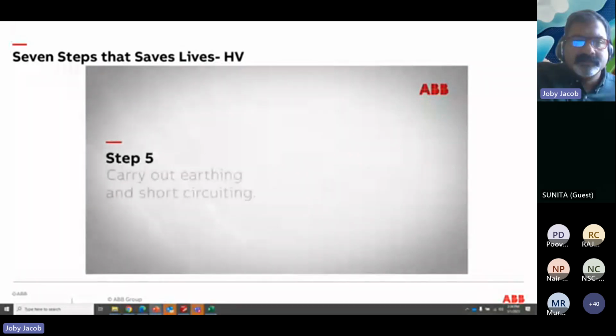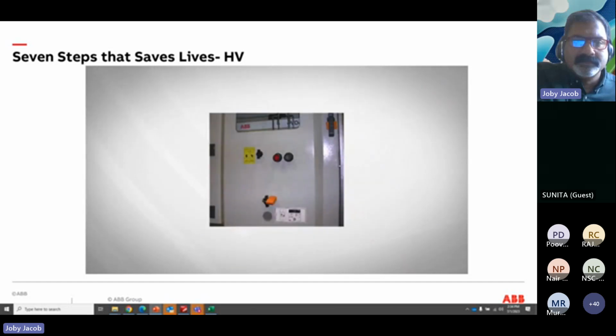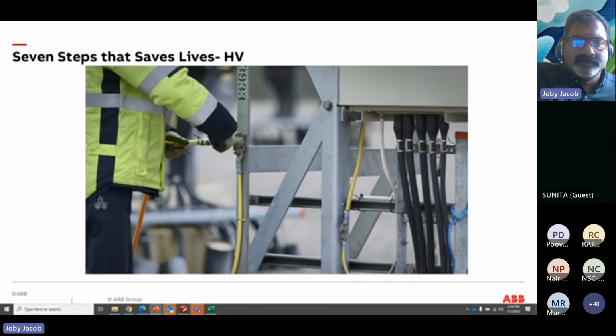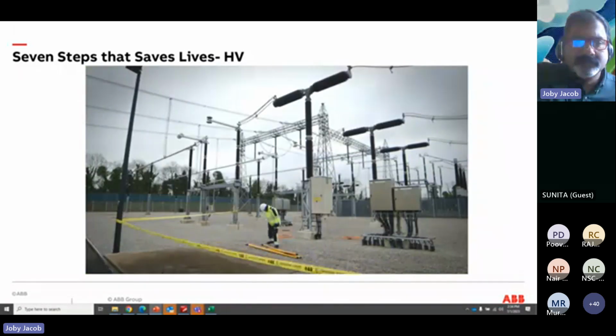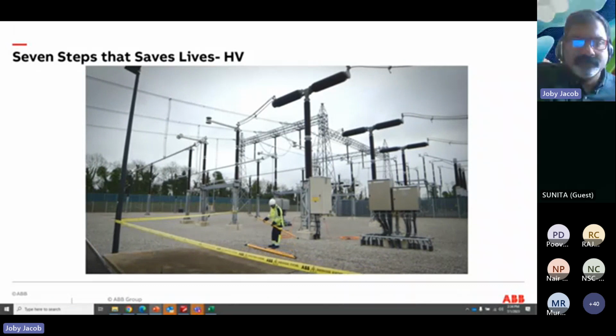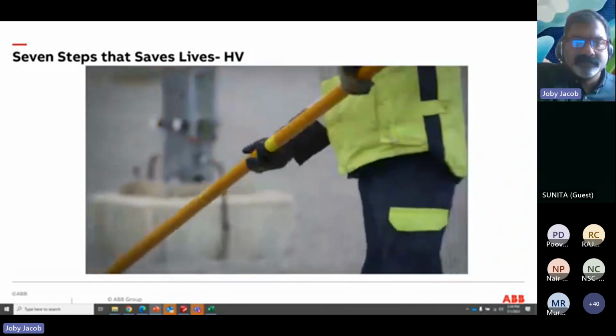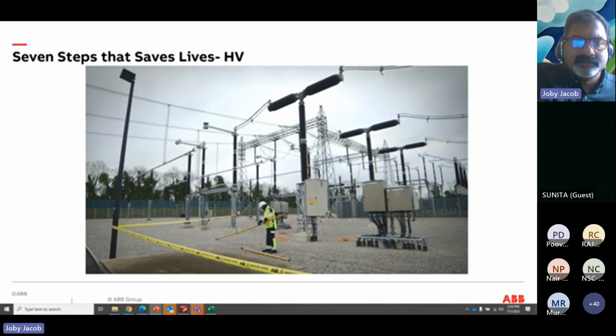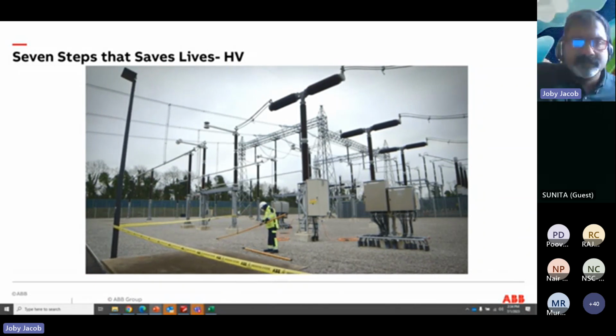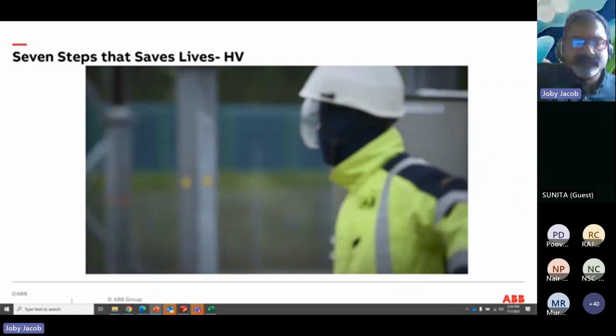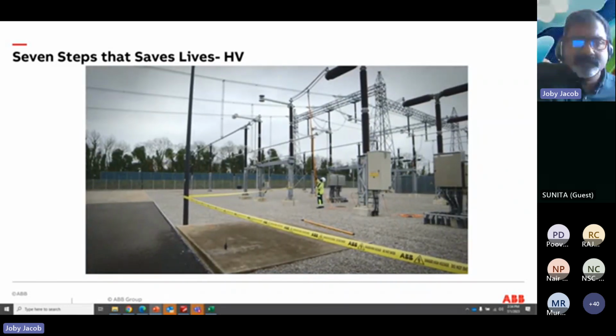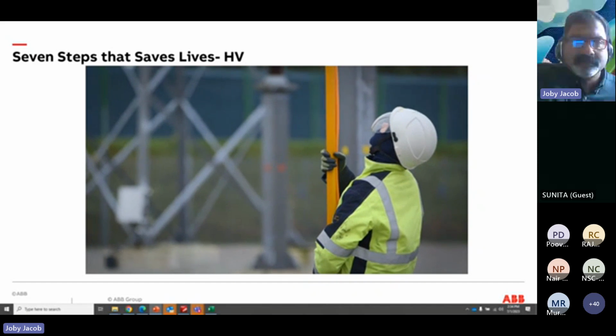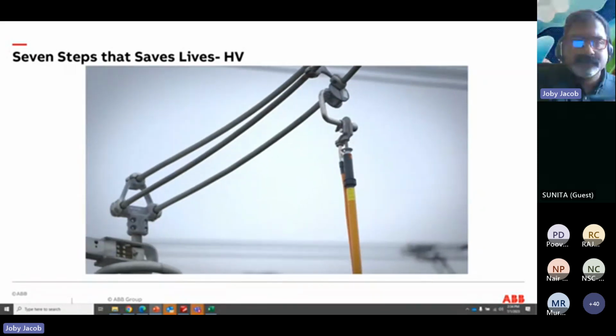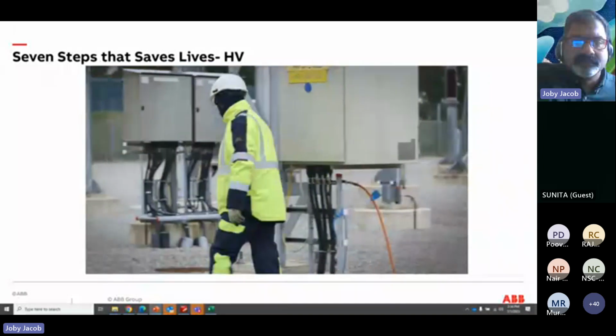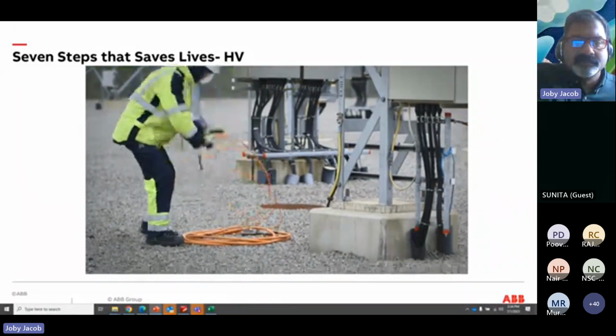Step 5. Carry out earthing and short-circuiting. Close and lock earthing switch if applicable, or apply portable equipment for earthing and short-circuiting while wearing the proper PPE identified in Step 1. Also, use insulated tools when required. Be sure the equipment is free of any residual charge or induced voltages and short-circuit any fault current. You may need multiple earths between supply sources and the point of work, commonly referred to as local earths. Ensure that you earth both sides of the apparatus being worked on.